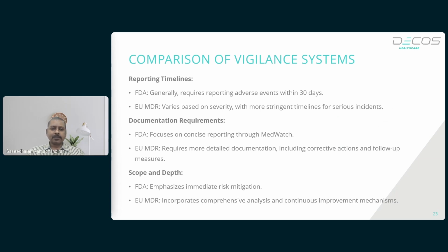The FDA focuses on concise reporting through the MedWatch system, emphasizing rapid submission to mitigate risk, whereas the EU MDR requires more detailed reports, including corrective actions and follow-up measures, with an emphasis on continuous improvement. The FDA prioritizes immediate risk mitigation, ensuring that potential threats to patient safety are addressed swiftly, whereas the EU MDR takes a more comprehensive approach, incorporating continuous analysis, long-term clinical follow-up, and regular updates to PMS plans based on real-world data.